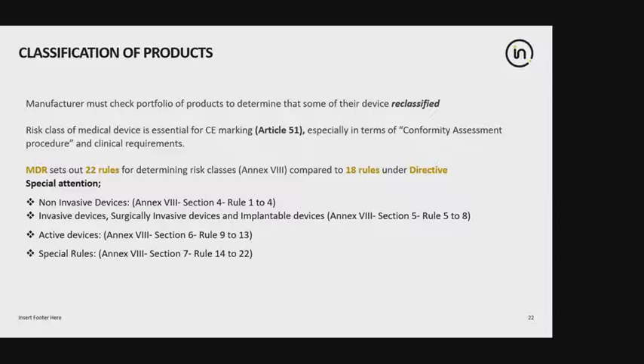Now, four sets of rules have been defined for the purpose of classification of the devices. Devices have been broadly categorized into a few categories. Non-invasive devices, for which the classification has been defined under Annex 8, Section 4, Rules 1 to 4. Non-invasive devices are those which do not necessarily penetrate inside the human body, which remain on the surface only or are used from the outside. Similarly, invasive devices, surgically invasive devices or implantable devices are covered under a separate set of rules. Active devices are those devices which need some source of energy for their operation, like an electrical source, to function. And there are other devices which come under the special rules.